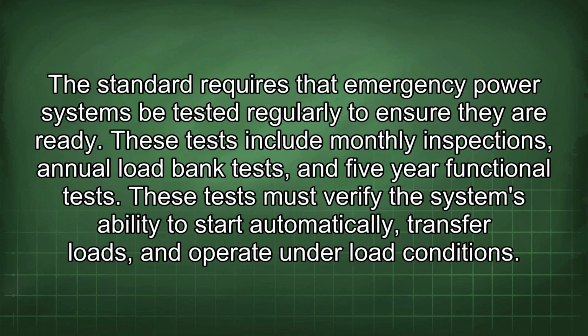The standard requires that emergency power systems be tested regularly to ensure they are ready. These tests include monthly inspections, annual load bank tests, and 5-year functional tests. These tests must verify the system's ability to start automatically, transfer loads, and operate under load conditions.